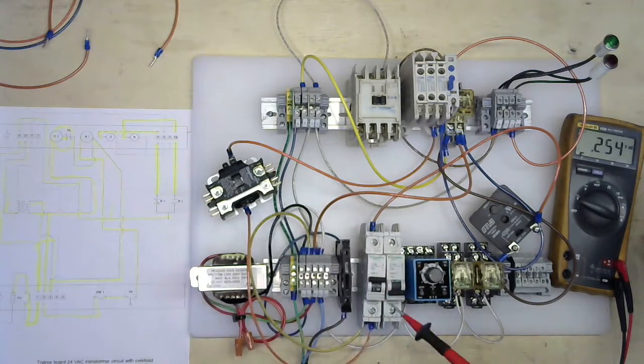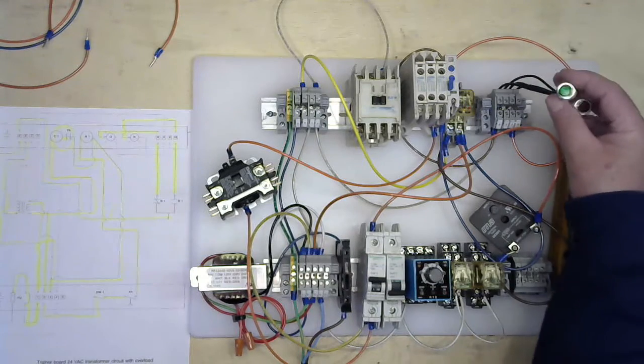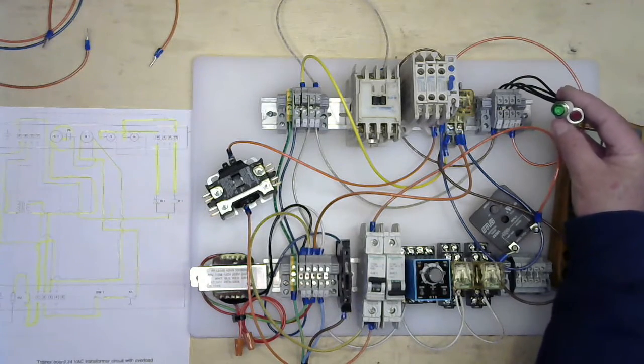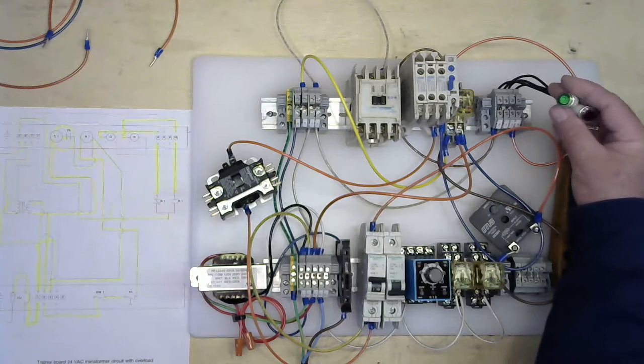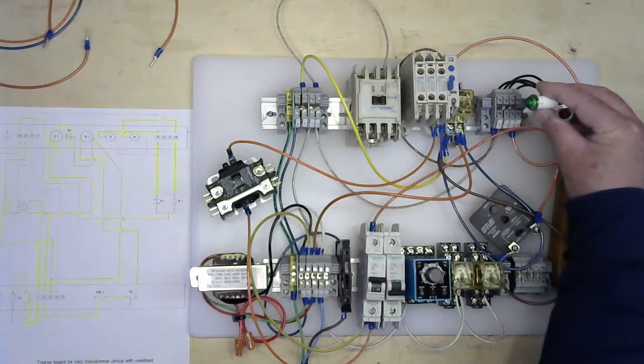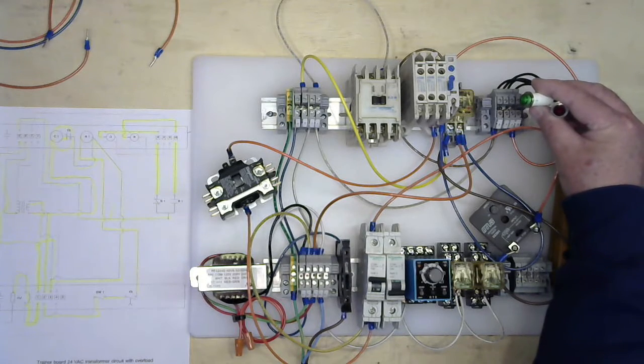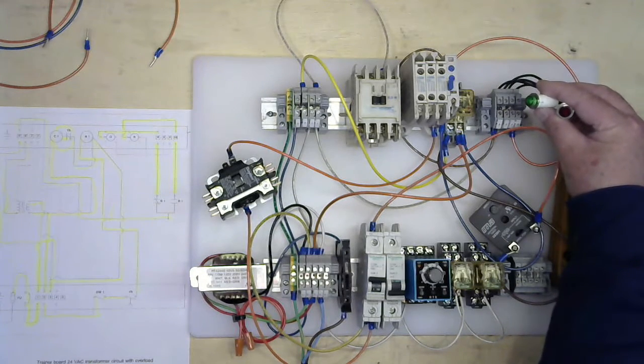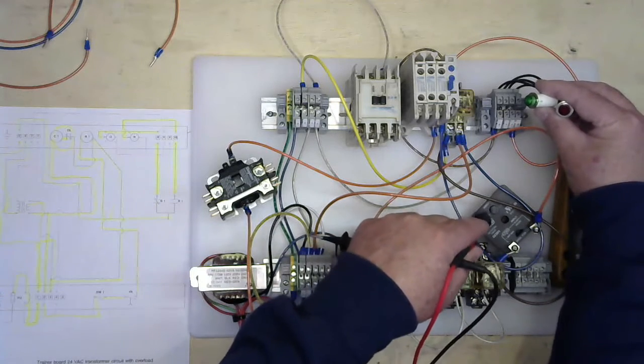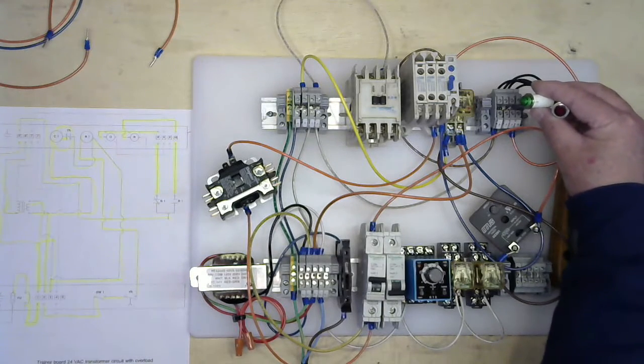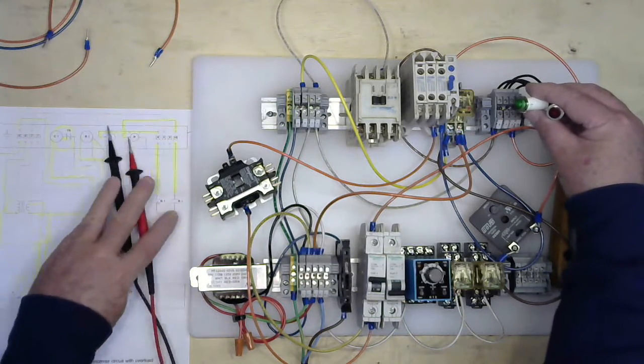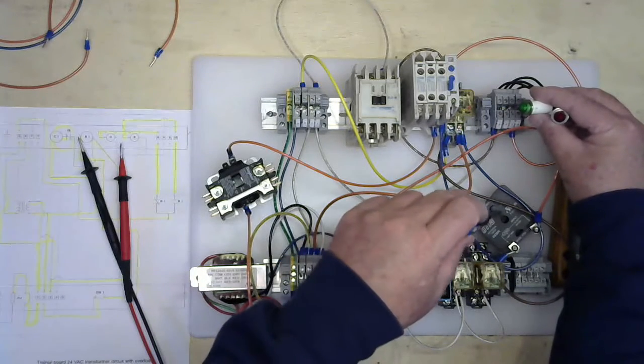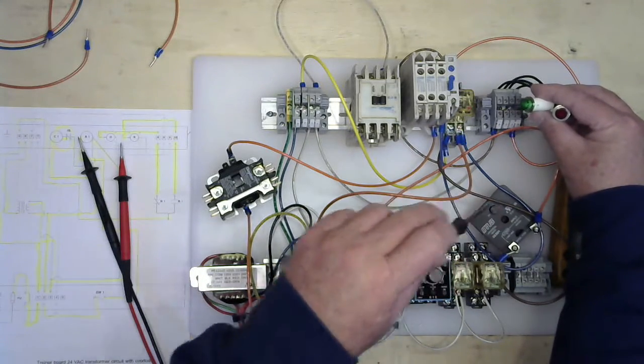If we energize our time delay relay and delay on make, we have a green light, no red light. And then once our time delay times out, it will change from a green to a red. As soon as you adjust your time delay, you can adjust it as high as you want, as long as you want. It's entirely up to you to get the setting that you want for that. This one's set a little longer. Let me see if I can just adjust it down just a little bit while it's still timing.